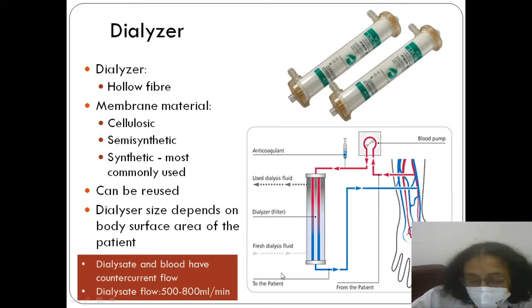So what is the dialysate? The dialysate basically starts with normal tap water, but obviously you cannot let the tap water come in contact with the patient's blood. It can cause serious reactions, infections, many complications. So there is a very sophisticated reverse osmosis plant in the dialysis unit which cleans up the water, and then electrolytes, acid and bicarbonate are added to that filtered water to create the dialysis fluid. We have to be very careful about the water being used in the dialysis fluid preparation, because in a 4-hour dialysis session a patient is exposed to around 120 to 200 liters of water, which is quite a lot. So you cannot afford to have any contamination in that water, and there are strict guidelines to prevent contamination. There should be no toxins, no colony forming units in the RO plant.